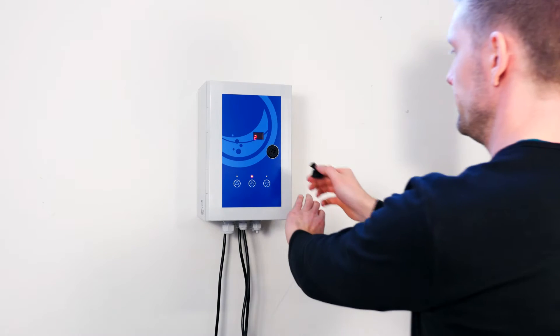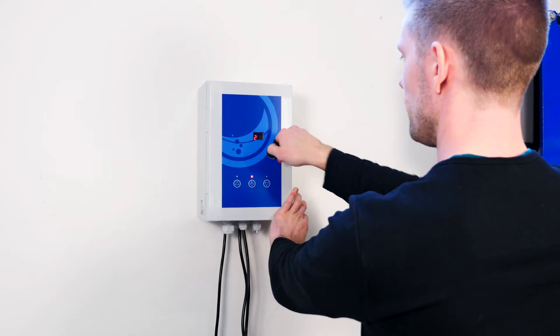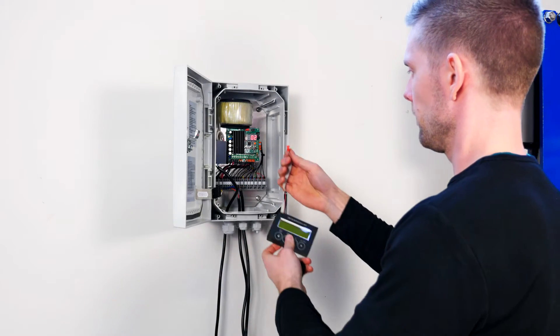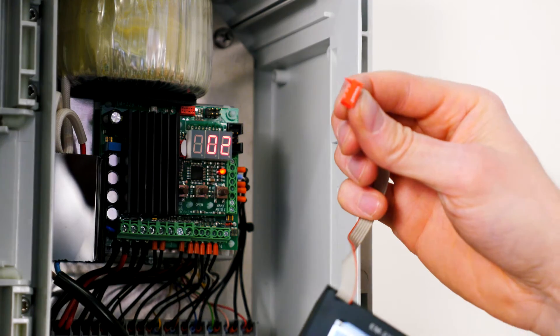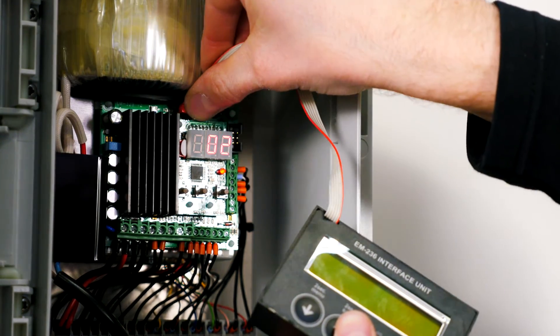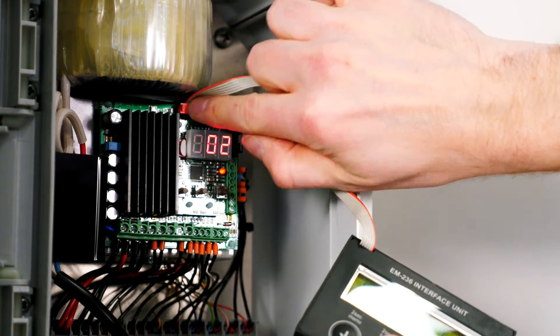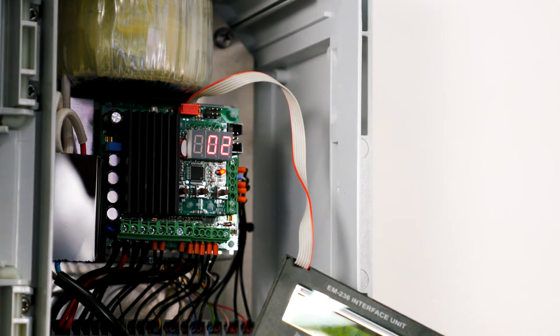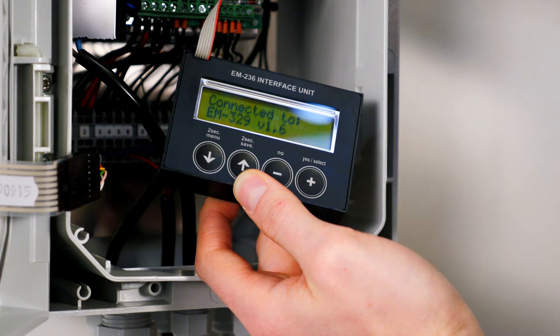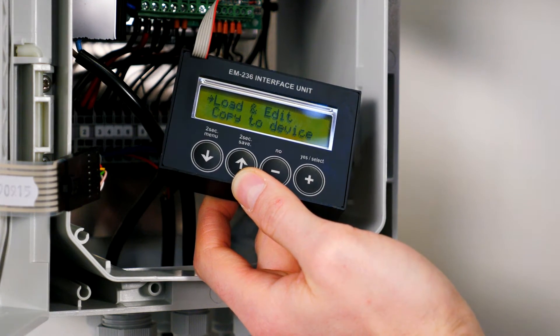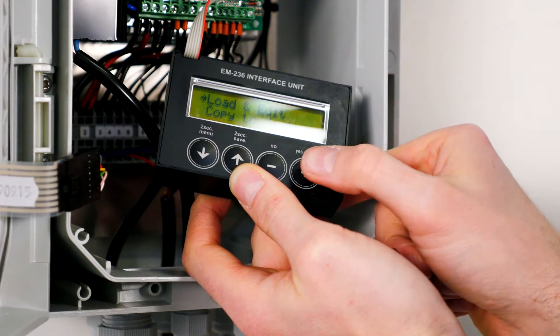Start by mounting the TR-EM236 programming module. This is done by opening the cover of the WCU, then mount the red plug in the counterpart, which is placed on the PCB up against the transformer. The programming module now writes connected to EM329, which is the WCU PCB.